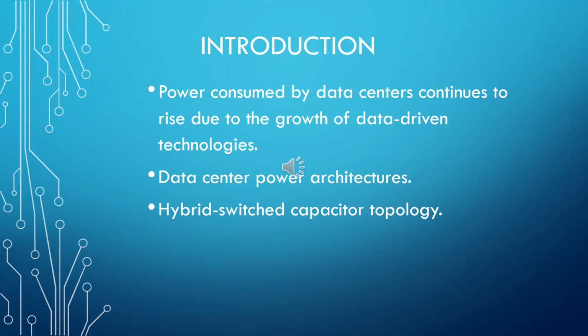That's where hybrid switch capacitor topology comes in, as it significantly enhances the power distribution system by reducing conduction losses. So we use a 48 volt bus, which has the advantage of simplifying wiring and reducing the number of power supplies required per rack, for point-of-load delivery distribution lines.